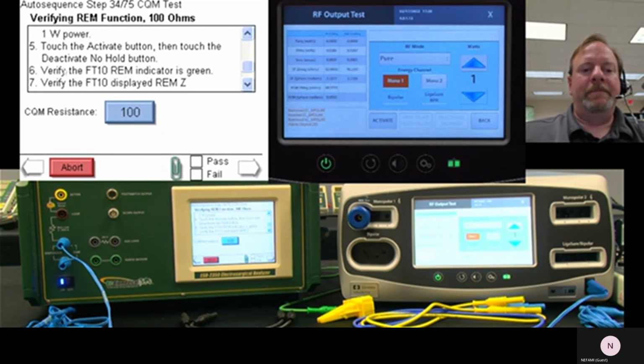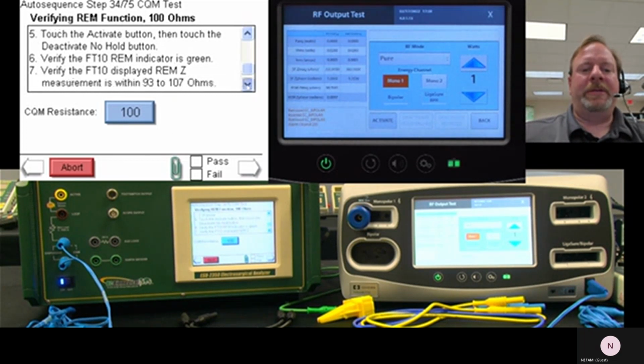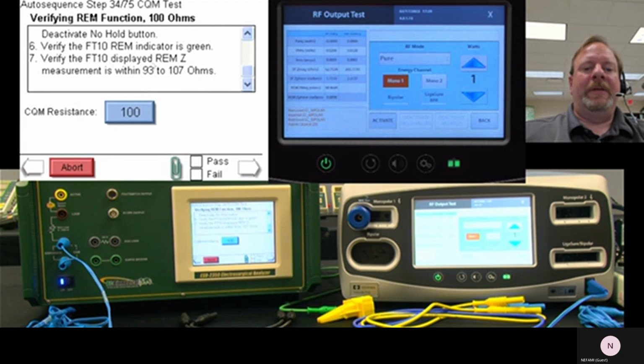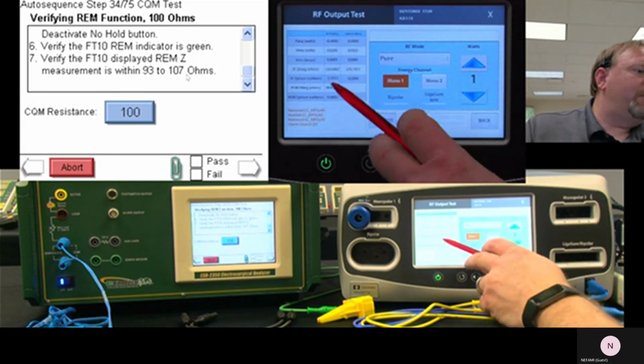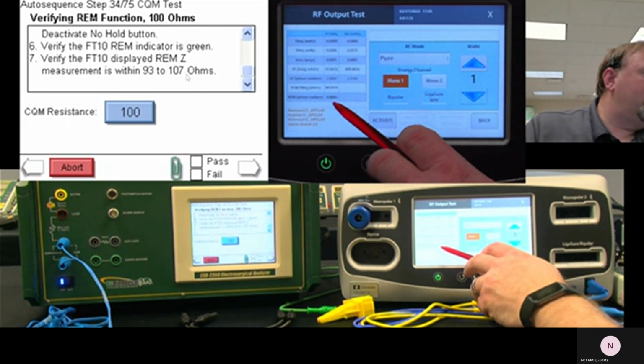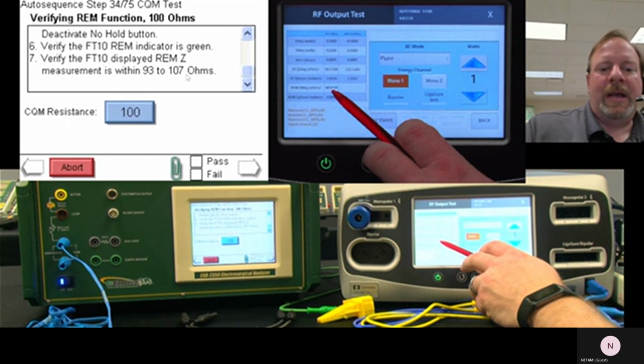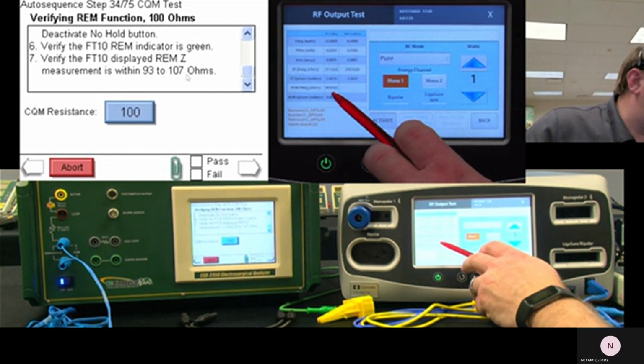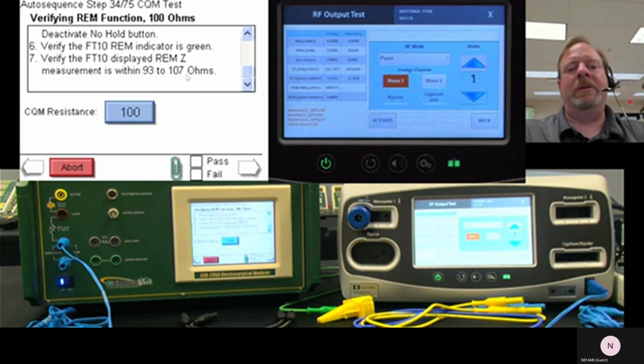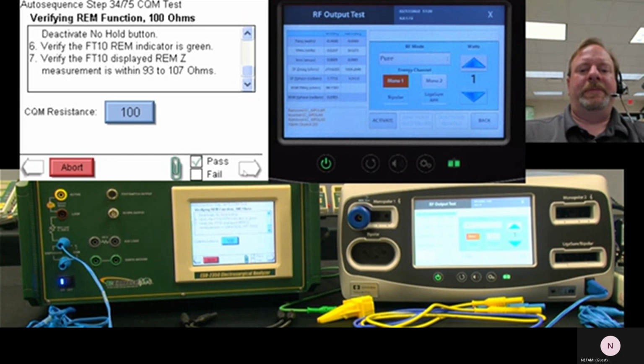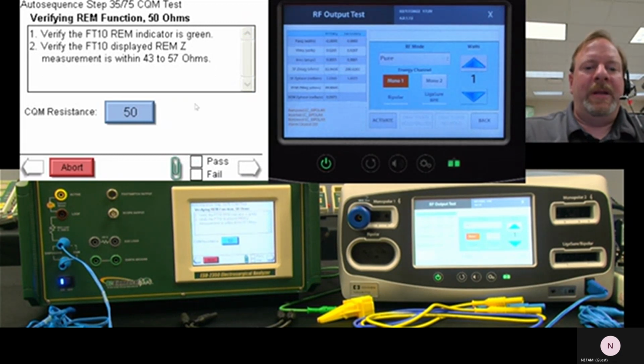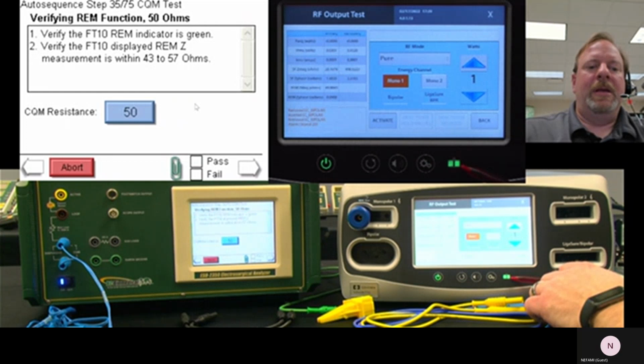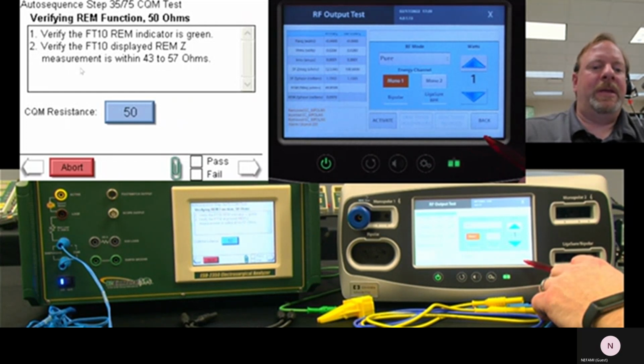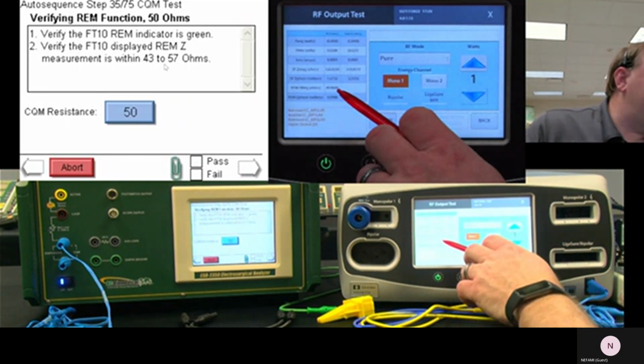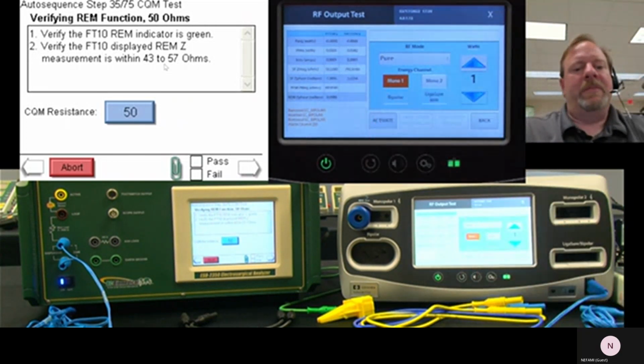So verify that the REM indicator is green. So verify the FT10 displayed REM Z is between 93 and 107 ohms. So this is the reading here, and it should be 93 to 107. I don't know if you can see it on your screen, but it's 98.9, 99.0. So we're good. So in this case, we'll say that passed. We'll move on to the next. Verify the REM indicator is green. Yes, it is still green. Verify the FT10 REM Z measurement is 43 to 57 ohms. In this case, it's 49.8. So I'm going to go ahead and say that's good.